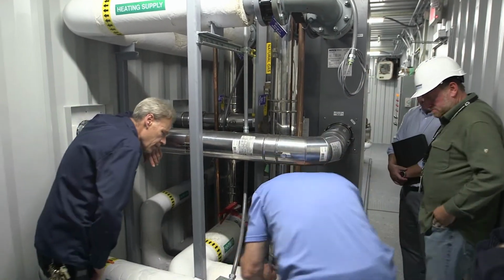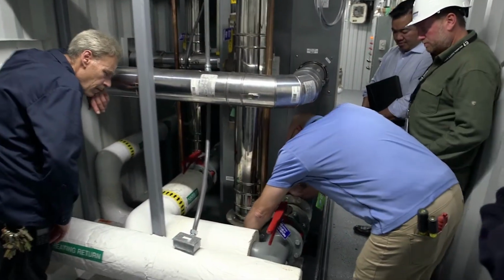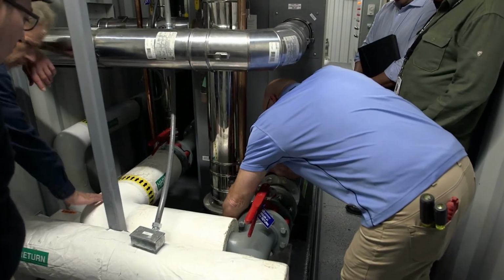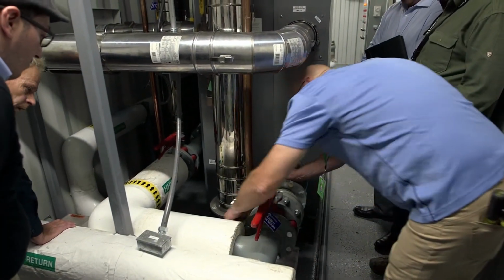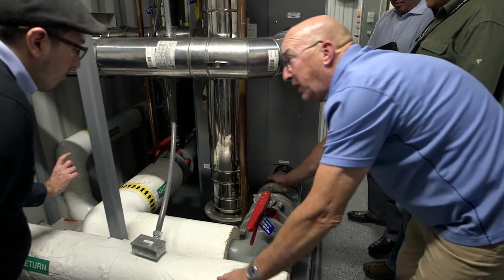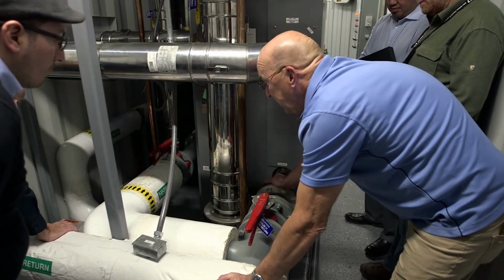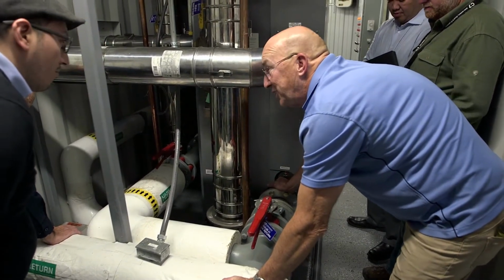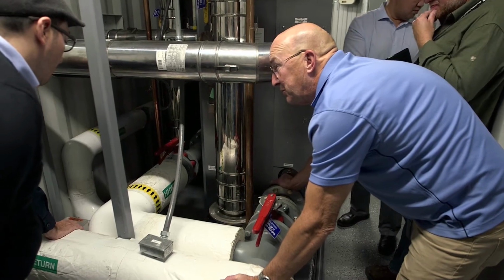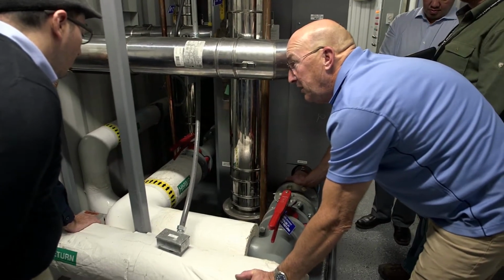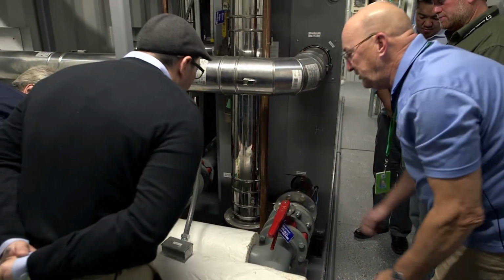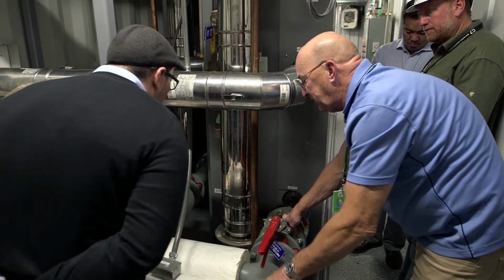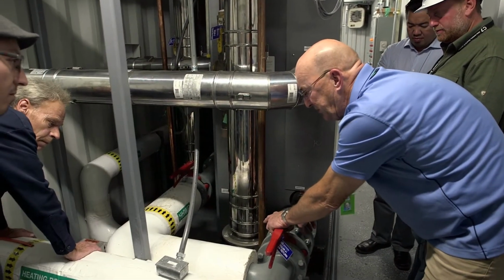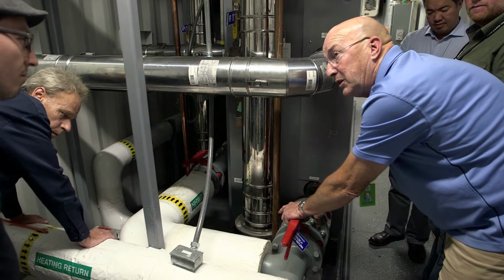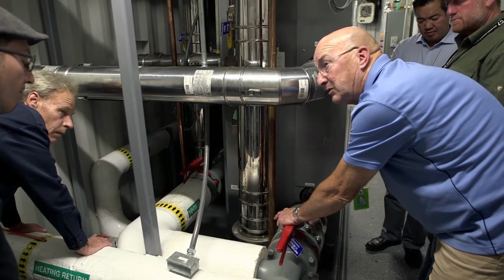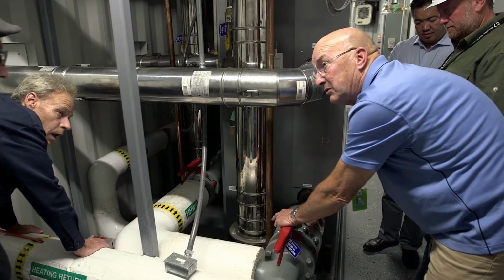This here, okay, this is your condensate trap, for the drain water coming out of the bottom of the boiler. You've got to check it and make sure it's clear and that the water's coming through. All right? The easiest way to check it, and this is once a year, no more than once a year, because you're not going to build up that much, all right?